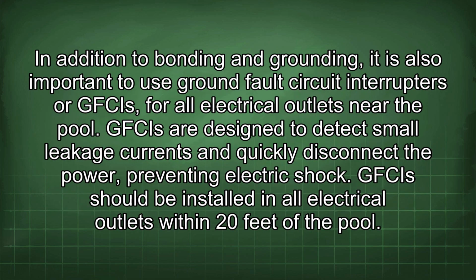In addition to bonding and grounding, it is also important to use ground fault circuit interrupters, or GFCIs, for all electrical outlets near the pool. GFCIs are designed to detect small leakage currents and quickly disconnect the power, preventing electric shock. GFCIs should be installed in all electrical outlets within 20 feet of the pool.